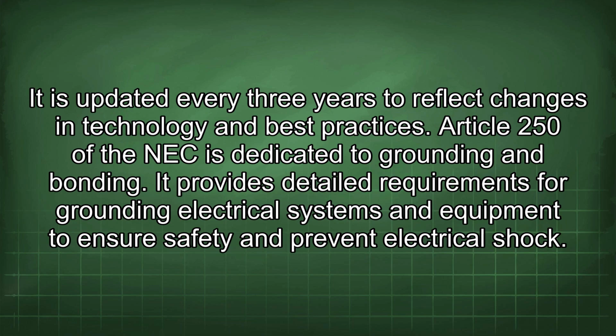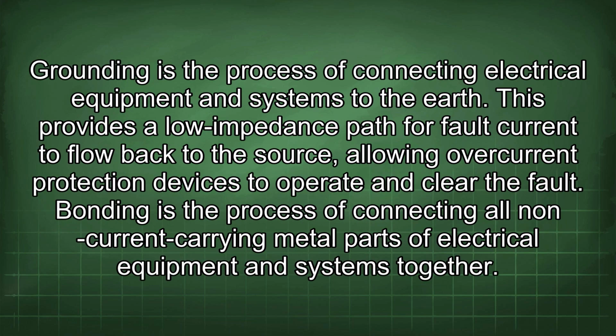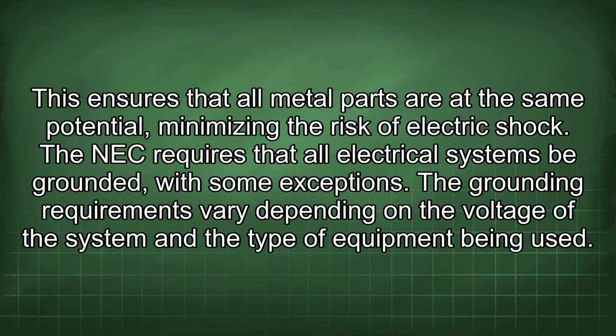Article 250 of the NEC is dedicated to grounding and bonding. It provides detailed requirements for grounding electrical systems and equipment to ensure safety and prevent electrical shock. Grounding is the process of connecting electrical equipment and systems to the earth. This provides a low impedance path for fault current to flow back to the source, allowing overcurrent protection devices to operate and clear the fault. Bonding is the process of connecting all non-current carrying metal parts of electrical equipment and systems together. This ensures that all metal parts are at the same potential, minimizing the risk of electric shock.